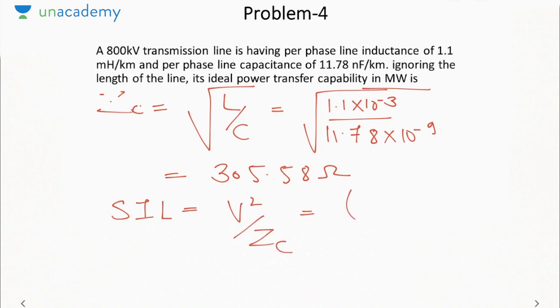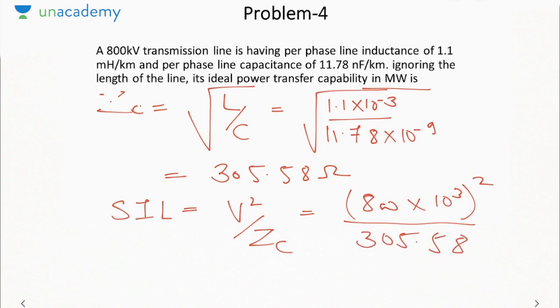To determine surge impedance loading, we will do V square by ZC, where V is the line to line voltage, 800 into 10 raised power 3 square, divided by 305.58. So it comes out to be 2094 megawatt. And why is it called as the ideal power transfer capability? Because at this power, sending end as well as receiving end power factor is unity, and we have a flat voltage profile on a transmission line. Hence it is the ideal power transfer capability.